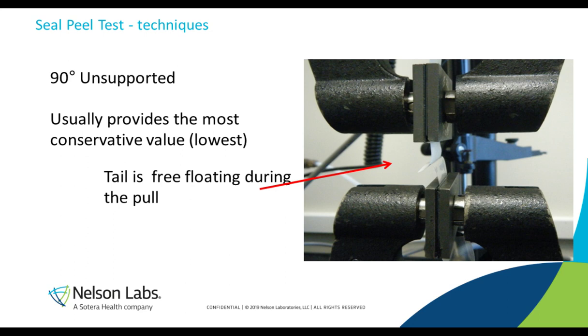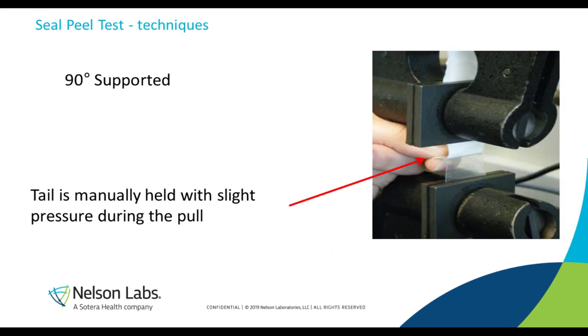There are a couple options when you're doing the seal peel test listed in the standard. This is the 90-degree unsupported. It is the most common and offers the most conservative value, or the lowest. The way that it works is the Instron or tensile machine grips the 2 legs and will pull apart, allowing the tail, which the red arrow is pointing to, to freely float in any direction as it's pulled apart. This will give you the lowest values.